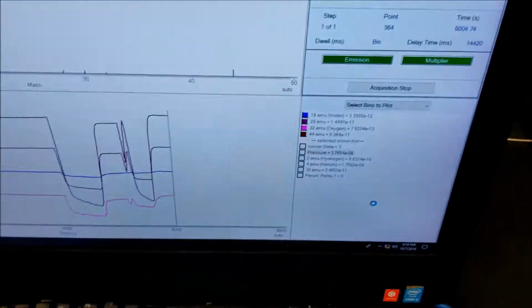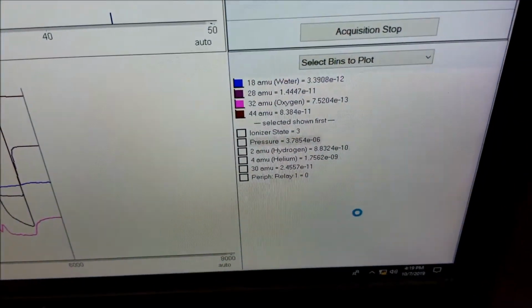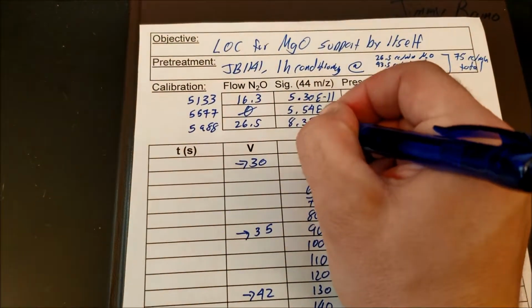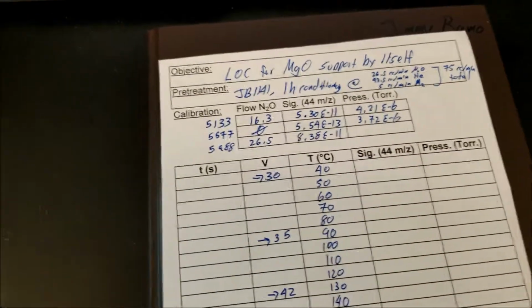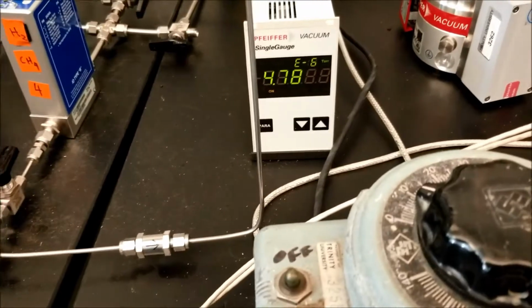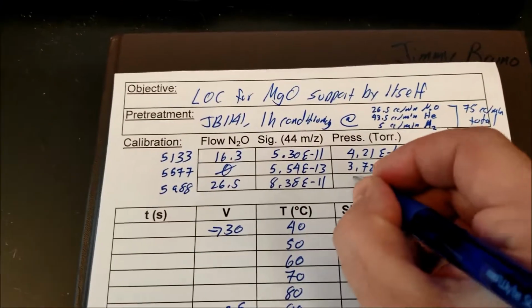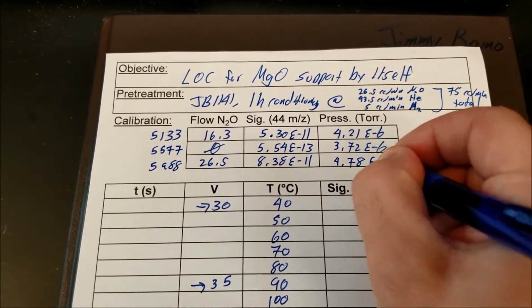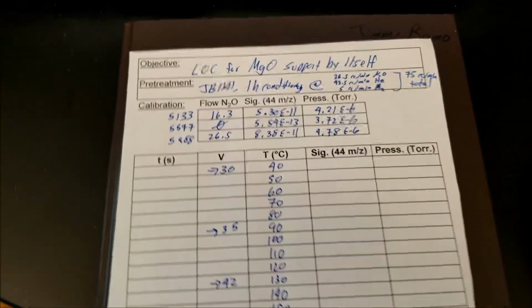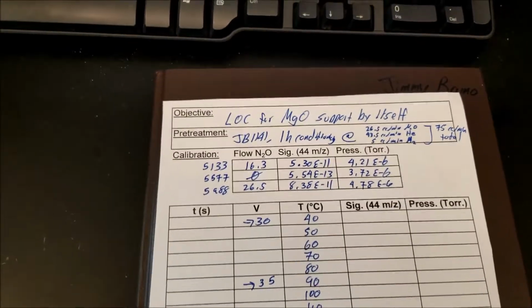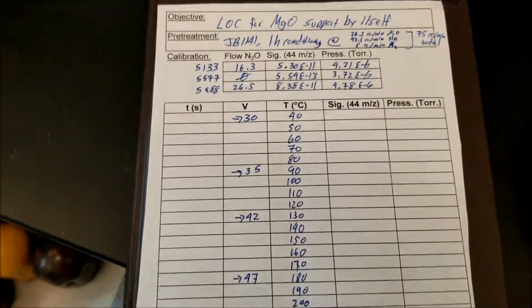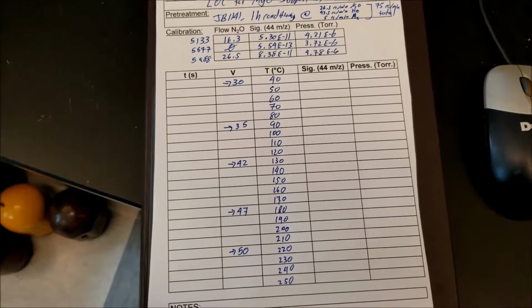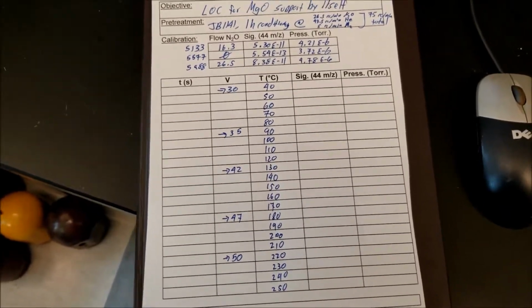This just changed over, but we'll pull off the data file itself. It's 8.38 E to the minus 11. And you also want to record the reading from the pressure gauge for the vacuum system, so 4.78 E to the -6. We're going to keep track of that during this test. It gives us a way to approximately correlate the signal drift of the N2O with the rise of the overall vacuum pressure in the vacuum system.